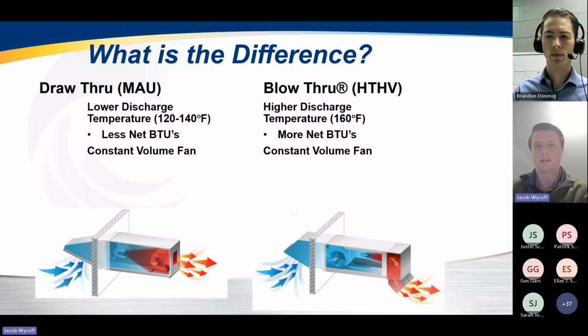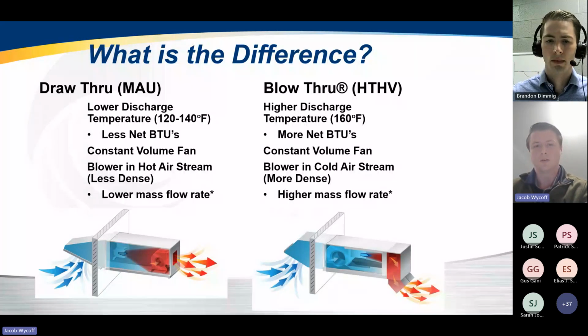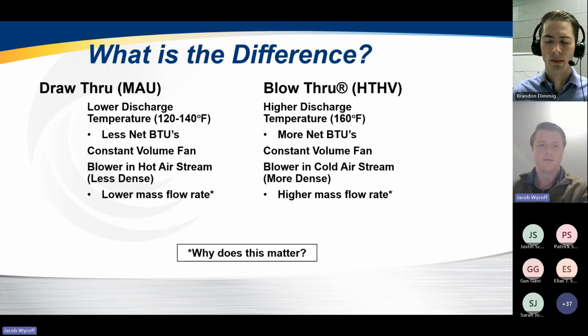But something we haven't talked about yet is that both of these units have constant volume fans. We're selecting our fans, we're talking about our fans, in relation to volume. But where we place that blower in relation to the burner has a huge effect on the density of the air that the fan is seeing. And why does that matter? Because the draw-through unit is seeing a much lower mass flow rate and the HTHV unit is seeing a much higher mass flow rate, it allows us to provide much more heat into the space per CFM, per volume of air that we're providing to the space.